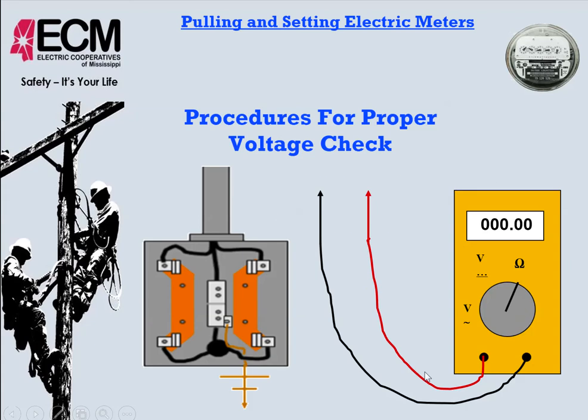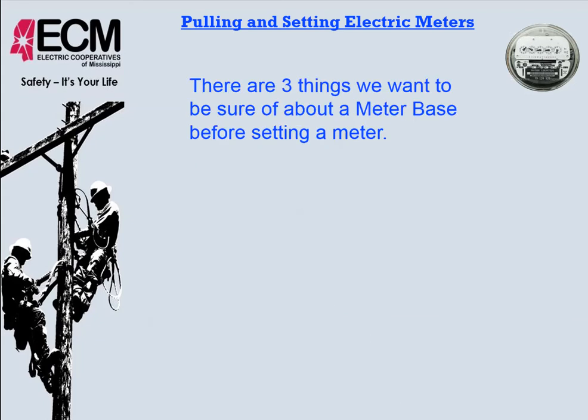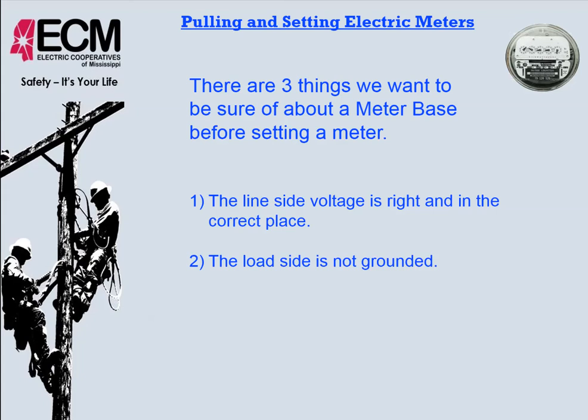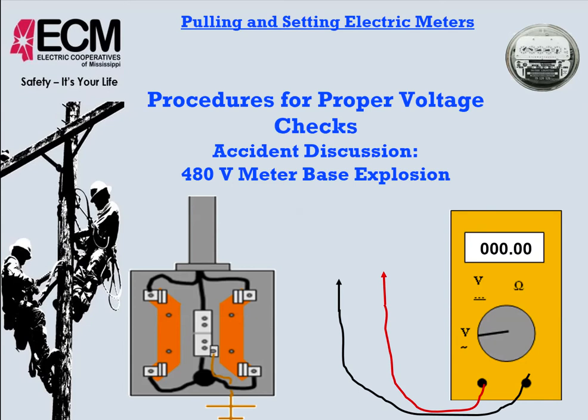Okay? So proper procedures for voltage checks, which is what we have now made our way to. I do want to talk to you about two accidents that occurred. I have some pictures of one of those as we go along. But there are three things primarily that we're looking for when we do the voltage checks inside of a meter base prior to setting a meter. One is that the line side voltage is right and in the correct place. The second thing is that the load side is not grounded, and then also that the load side is not tied together.